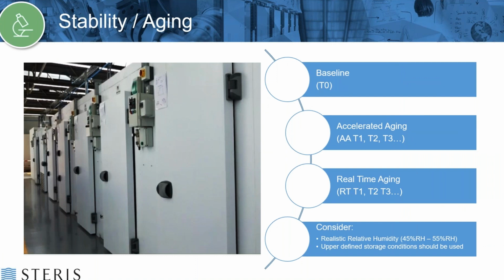So you're also going to do stability or aging testing. As we talked about a few moments ago, there's baseline testing at time 0. This will be your product comes through your worst case sterilization process and goes immediately to testing. Sometimes people will use their distribution samples as their baseline as well. Most people will do accelerated aging, technically not required. The real-time aging is required per ISO 11607, but almost everyone does accelerated aging.